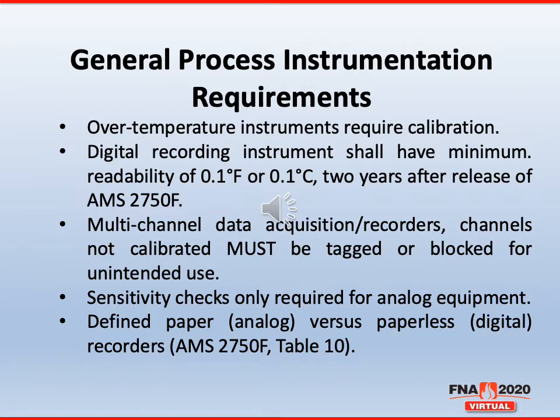The new requirement is that the readability will be 0.1 Fahrenheit or 0.1 Celsius, depending on where you're processing, 2 years after the release of AMS 2750F. So June of 2022, there's going to be a requirement that your data acquisition will have to have 0.1 readability, Fahrenheit or Celsius. This is actually fixing a flaw within the specification. It's twofold. For those who are processing in Celsius and you had a requirement of your instrumentation to be plus or minus 1.1, and your data acquisition system did not have 0.1 readability, then how would you show compliance?